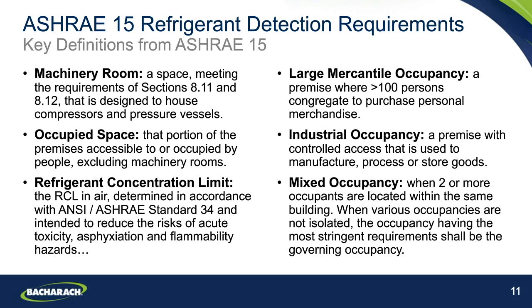An occupied space, of course, is fairly self-explanatory. It is that portion of premises that is accessible or occupied by people, but the one thing to note there specifically is that the occupied space definition excludes machinery rooms, and there are some specific references within the standard that are focused in machinery rooms. And the refrigerant concentration limit is important. This is the definition of the concentration in air that is determined to present a risk. So the limits in place are calculated there to reduce those risks of acute toxicity, asphyxiation, and flammability, which of course we've just mentioned with respect to the different gases that are being used.